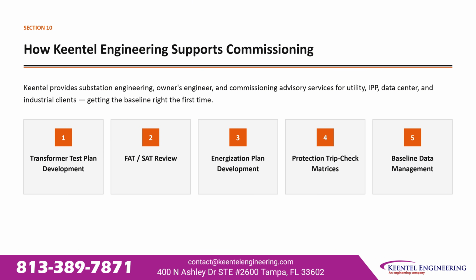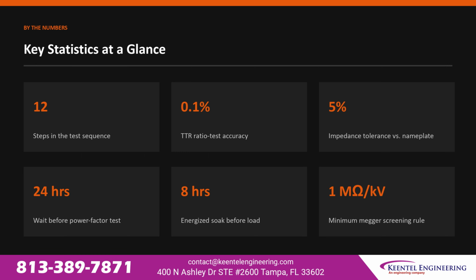and baseline data management. Let's recap the numbers behind this process. 12 steps in the test sequence. TTR accuracy of 0.1%, an impedance tolerance of 5% versus nameplate, a 24-hour wait before power factor testing, an 8-hour energized soak before load, and a minimum Megger screening rule of 1 megohm per kilovolt.